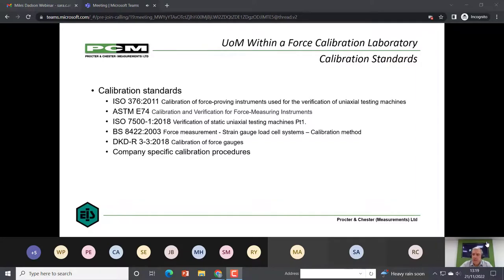There are several calibration standards that either type of calibration source can calibrate to, and just a few here. The gold standards, the top two, are 376 and the American version, E74. The calibration frames that we have, load cell primary load cells, are calibrated to 376. A lot of calibration facilities will use 7500, which is a calibration of the entire frame.